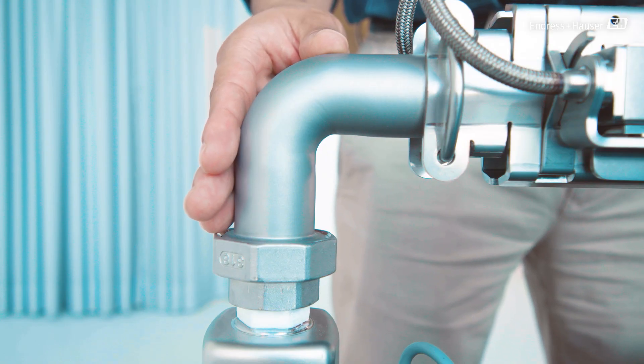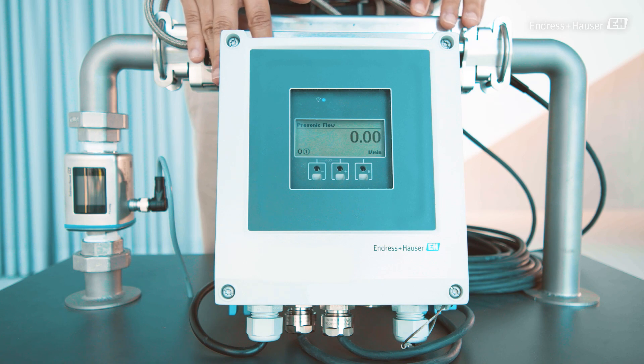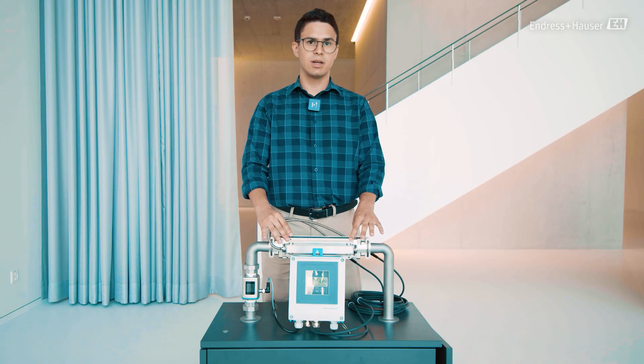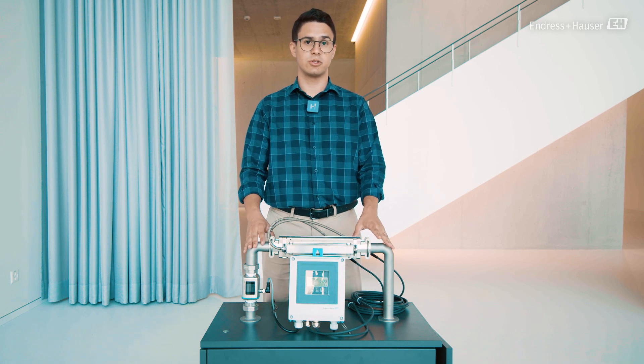A stainless steel pipe of one inch, and here we have our Prosonic Flow W400 with two sensor sets of 5 megahertz installed at 180 degrees from each other with one traverse sensor positioning.